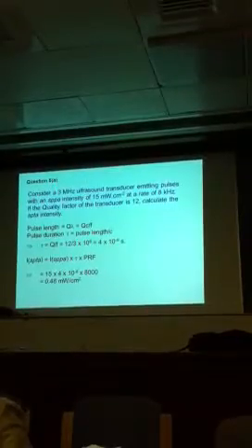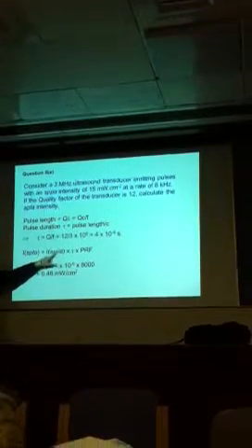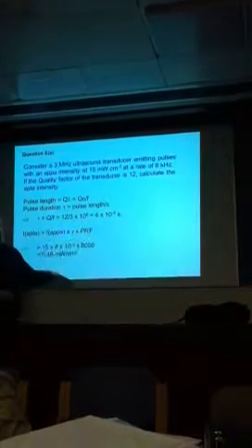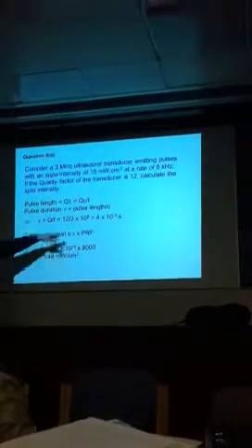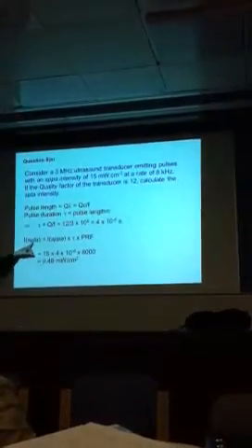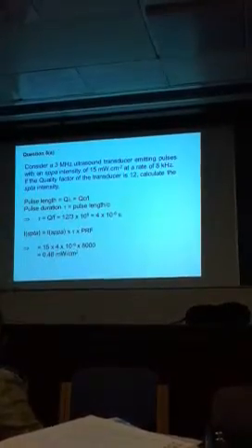Now, this formula is given in the notes. If you don't remember it in the exam, it's possible that you could derive those principles. Spatial peak temporal average intensity is equal to spatial peak pulse average intensity times pulse duration times the pulse repetition frequency. That's the rate at which pulses are emitted into the tissue, and we're told that's 8 kilohertz. Therefore, put those numbers in, and you get the spatial peak temporal average comes out as 0.48 milliwatts per square centimetre. Relatively straightforward calculation.